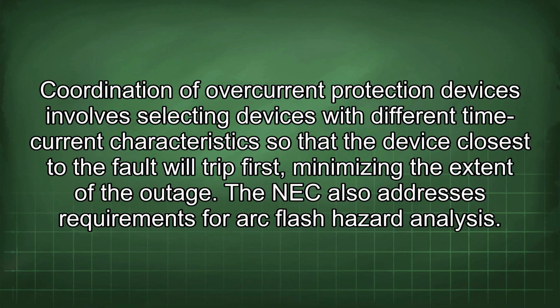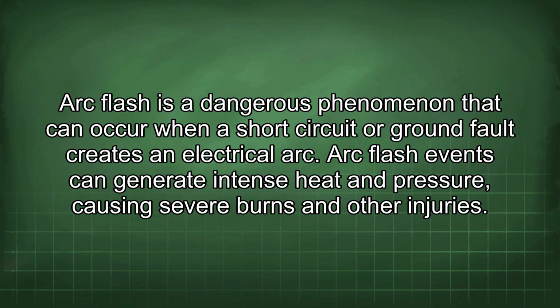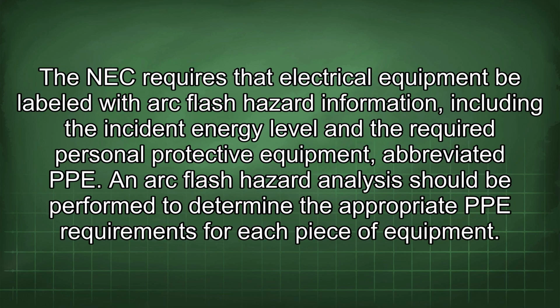The NEC also addresses requirements for arc flash hazard analysis. Arc flash is a dangerous phenomenon that can occur when a short circuit or ground fault creates an electrical arc. Arc flash events can generate intense heat and pressure, causing severe burns and other injuries. The NEC requires that electrical equipment be labeled with arc flash hazard information, including the incident energy level and the required personal protective equipment, abbreviated PPE. An arc flash hazard analysis should be performed to determine the appropriate PPE requirements for each piece of equipment.